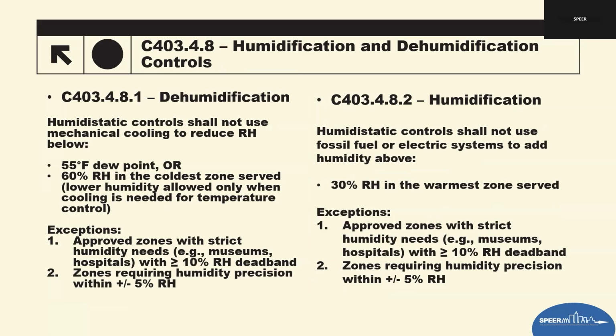Humidity control is one of the biggest energy use drivers in commercial buildings, especially in Texas. The IECC sets limits on both dehumidification and humidification to prevent overconditioning and wasting energy. So now there is a humidification, dehumidification control. On the dehumidification limits, the first rule is about how low mechanical cooling is allowed to reduce humidity. Mechanical cooling cannot drive humidity below 55 degree dew point or 60% relative humidity, whichever is lower. This ensures systems aren't running cooling aggressively just to chase extra dry air. This wastes a ton of energy.